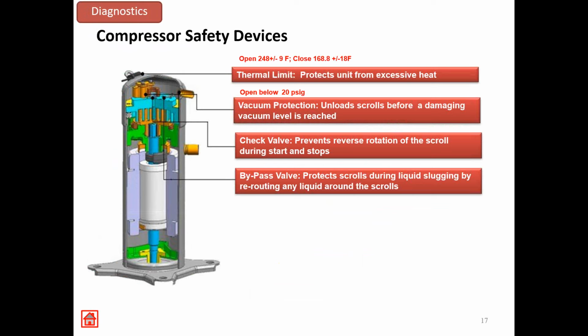Outside of that, the internal device from Copeland, we cannot register anything from it. When it comes to vacuum, it's vacuum protected. You cannot pull the system down more than 20 psi. Once you get there, it's going to stop and do an internal relief on itself, and you'll have to stop the compressor and then recover the remaining amount of refrigerant left in the system.